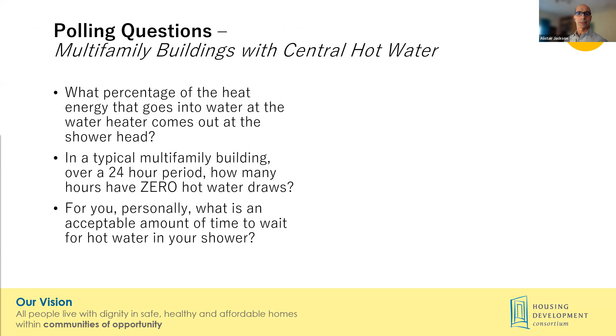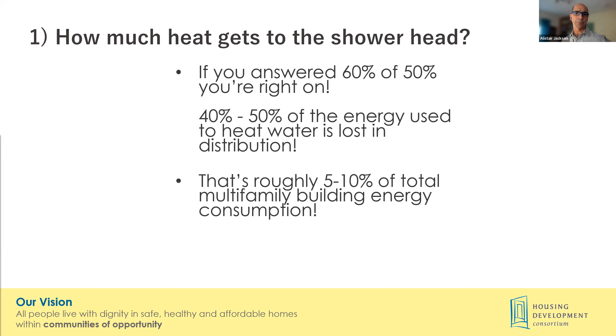So how much heat gets to the shower head? If you answered 60% or 50%, you're right on the money. Roughly 40 to 50% of the energy used to heat the water is actually lost in the distribution system, one reason to focus on distribution as well as equipment efficiency. That's actually 5 to 10% of total multifamily building energy consumption, which is significant. While it does help heat the building, that heat is being lost inside the building, not really where you want it, and it also adds to the cooling load in the summertime. As we wrestle with keeping buildings cool during high temperature events, losing a lot of heat from that 120-degree loop is pretty significant.